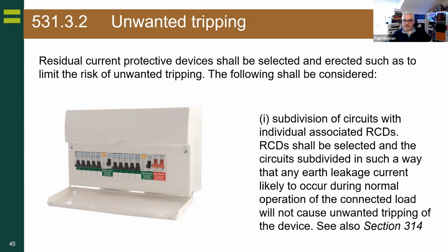So bullet point 1, subdivision of circuits or individually associated RCDs. RCDs should be selected and the circuits divided in such a way that any earth leakage occurring in normal operation of the connected equipment will not cause unwanted tripping. Now, most people will say this is the death of the split load board. If you think about it, in a domestic house like mine, in theory, I could put in a split load type A RCD, measure my leakage, and as long as it's within tolerance, it's fully compliant.